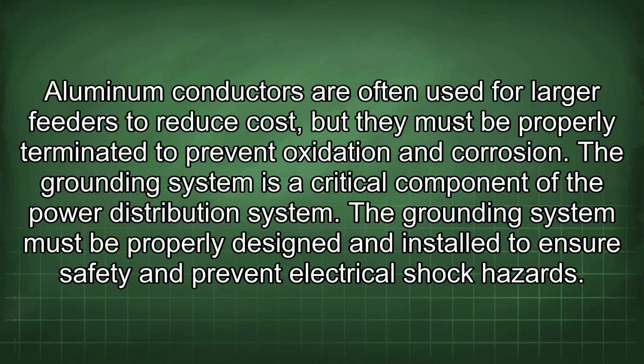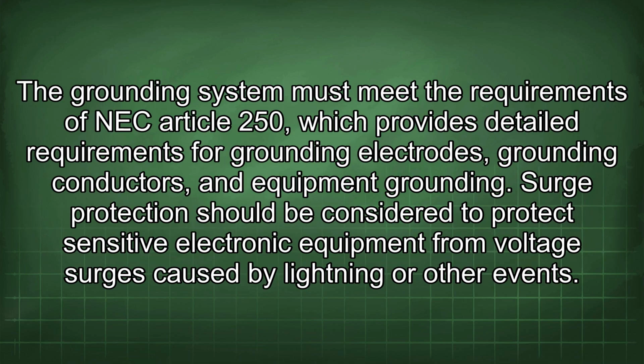The grounding system must be properly designed and installed to ensure safety and prevent electrical shock hazards. The grounding system must meet the requirements of NEC Article 250, which provides detailed requirements for grounding electrodes, grounding conductors, and equipment grounding.